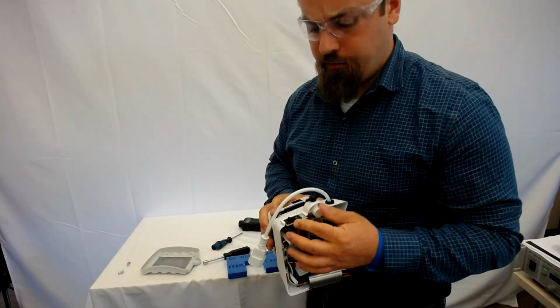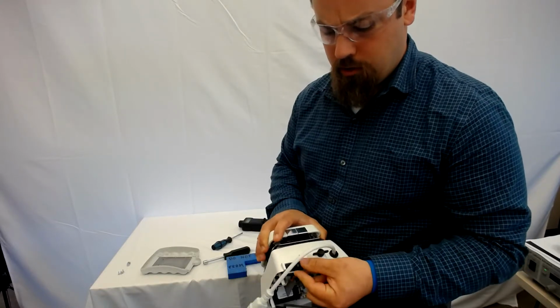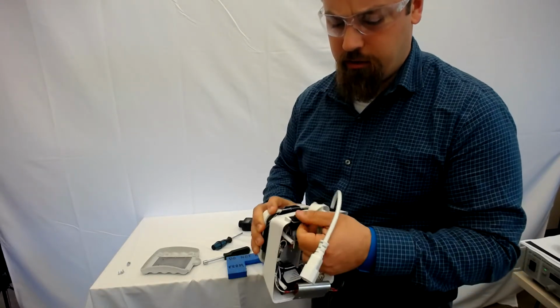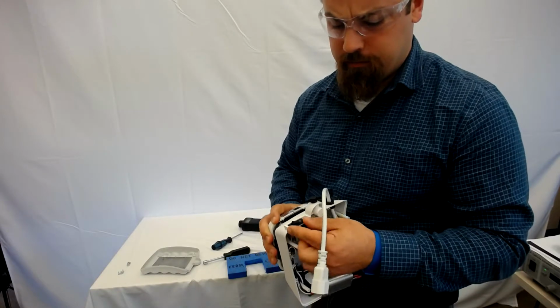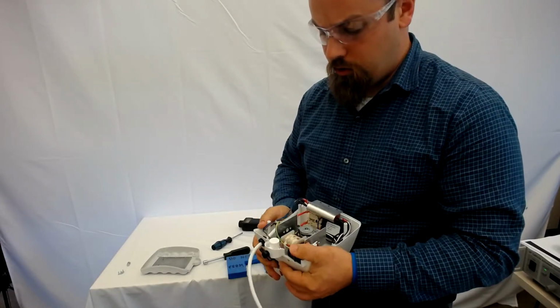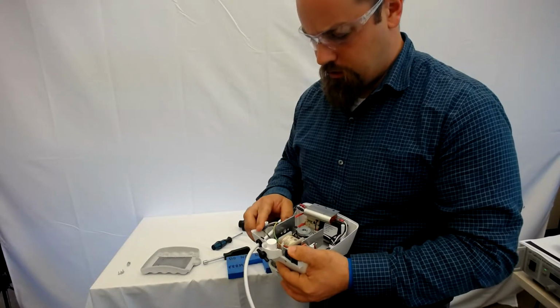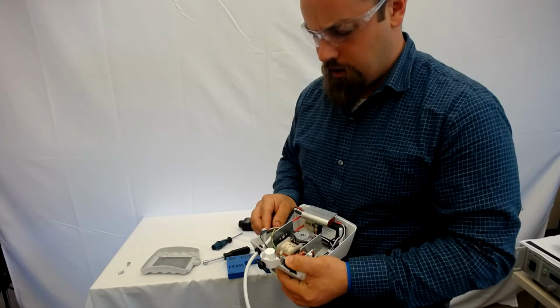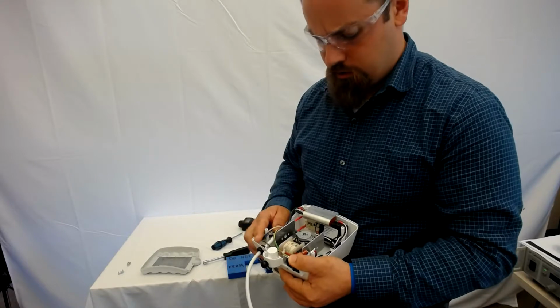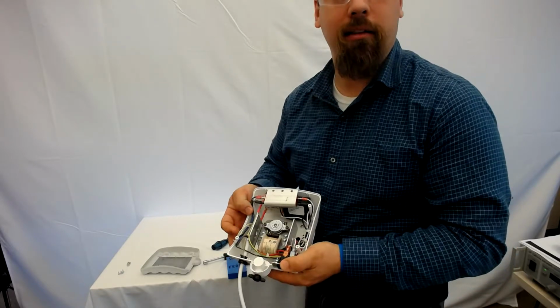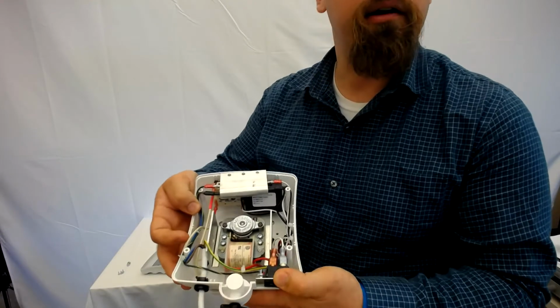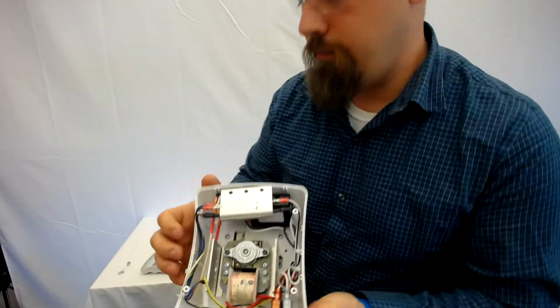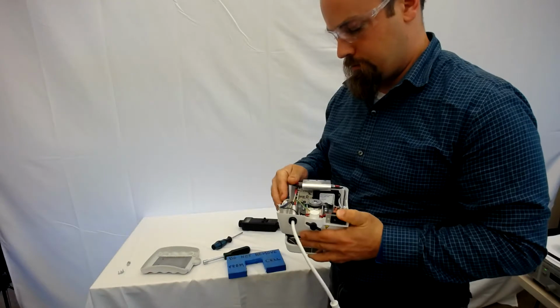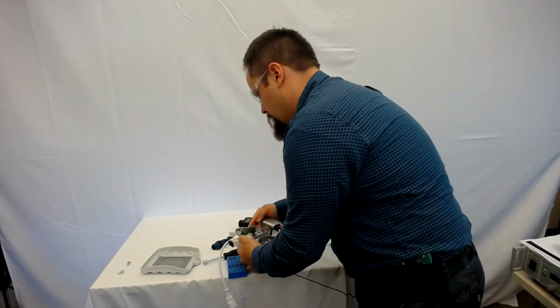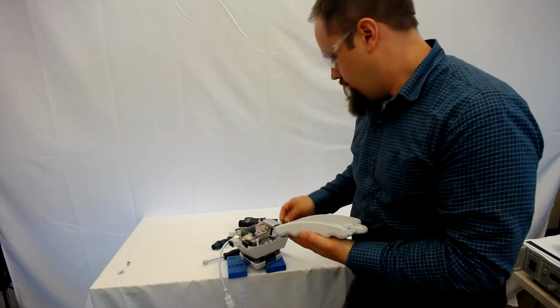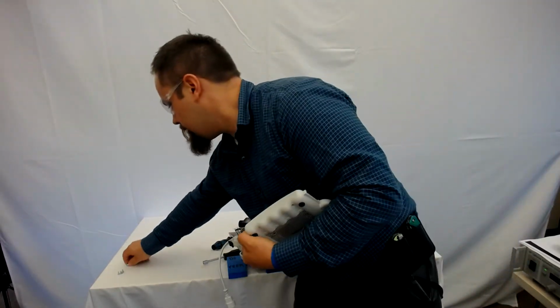As you're reassembling, if it's a heating unit that has the switch, you want to make sure that it's aligned correctly in the back. On all units, you want to make sure that the wire routing is correct and cannot be pinched when the unit is put back together. So a nice, neat interior here is very important. All right. Next, we're going to put the filter back on.